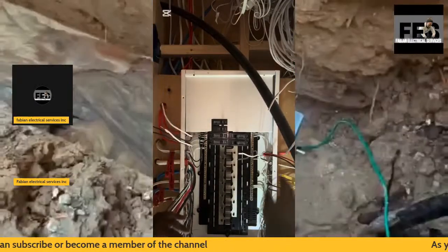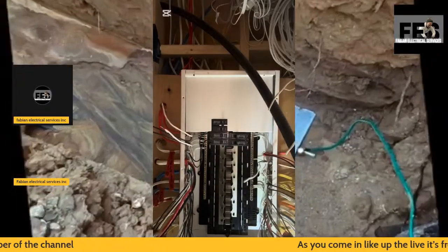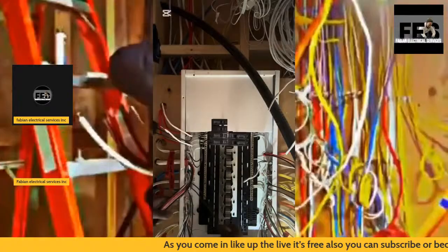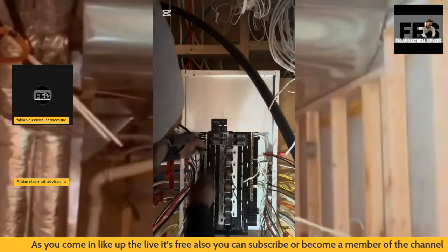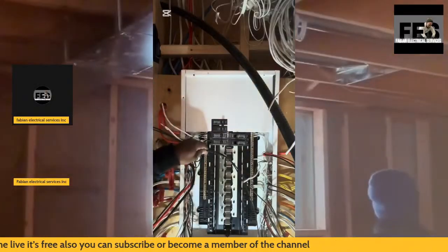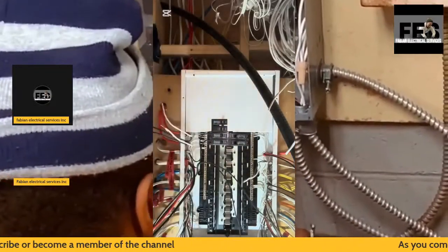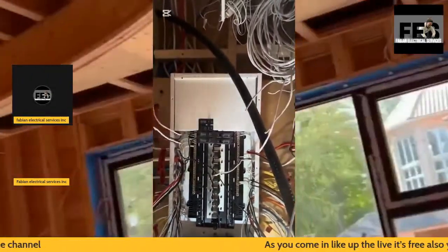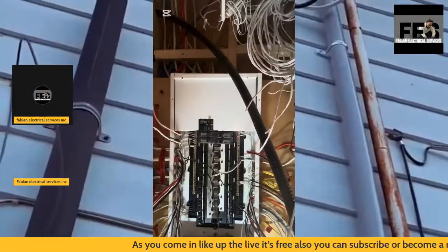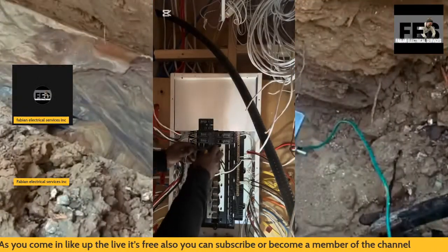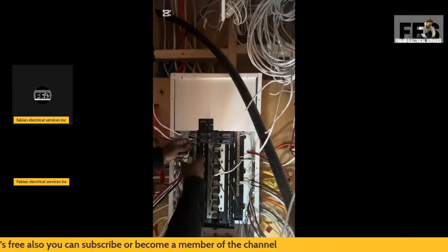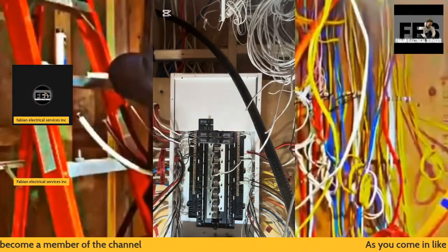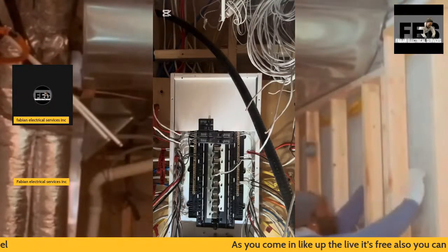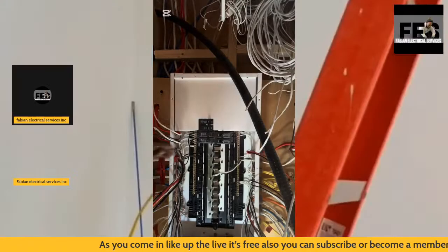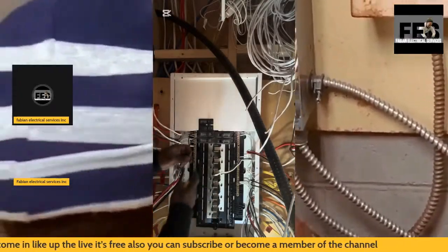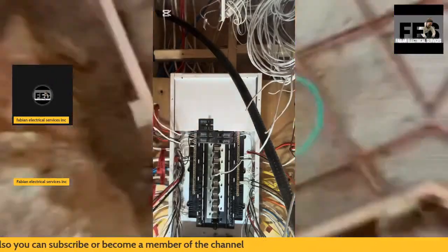A lot of times, sometimes in those kitchens, you'll see, let's say, someone is using a 15 amp receptacle. They're going to mix and mingle all of these other things onto the electrical circuit, and what ends up happening is that circuit will end up tripping because you didn't size the breaker or the wire properly, and it's going to be a nuisance. So it's better when you're running your wires inside of residential homes, just make sure you have the proper size wire again, and the proper size breaker.